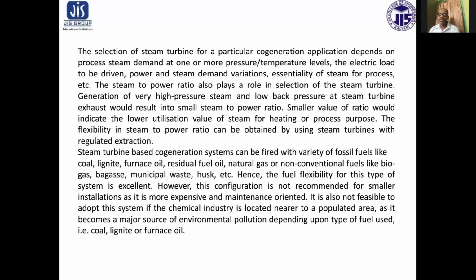Steam turbine based cogeneration systems can be fired with a variety of fossil fuels like coal, lignite, furnace oil, residual fuel oil, natural gas, or non-conventional fuels like biogas, bagasse, municipal waste, husk, etc. Hence, the fuel flexibility for this type of system is excellent. However, this configuration is not recommended for smaller installations as it is more expensive and maintenance oriented. It is also not feasible to adopt this system if the chemical industry is located near a populated area, as it becomes a major source of environmental pollution depending upon the type of fuel used, that is coal, lignite or furnace oil.